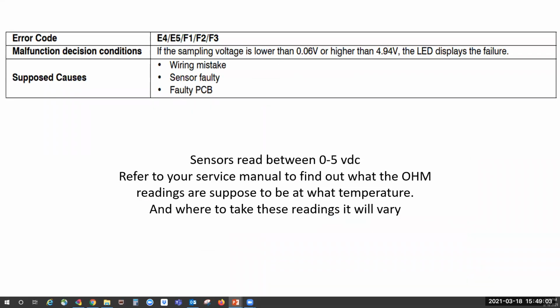Sensors, E4, E5, F1, F2, F3. Sensors usually operate between 0 and 5 volts DC. It's a good idea to, once again, just check your service manual for these exact readings. The sensors play a big role in defrost, fan speeds on indoor and outdoor unit, compressor speed, what it's operating at.